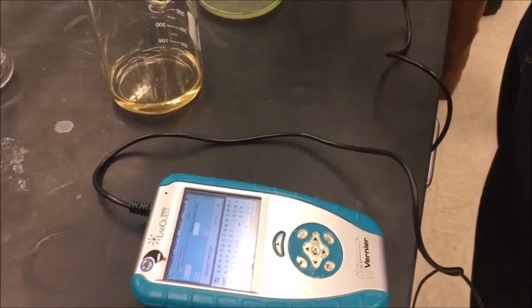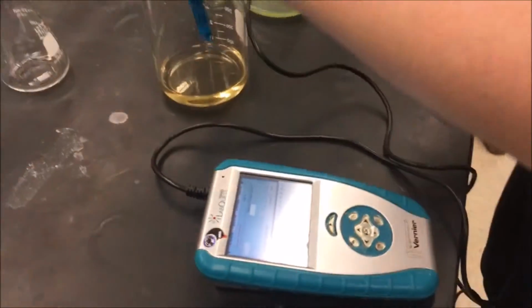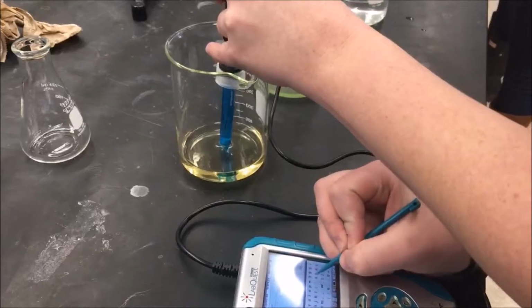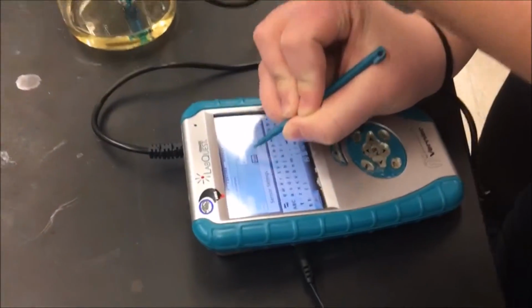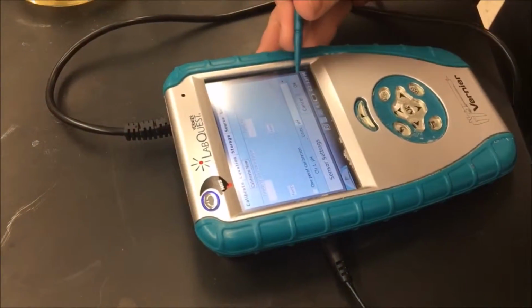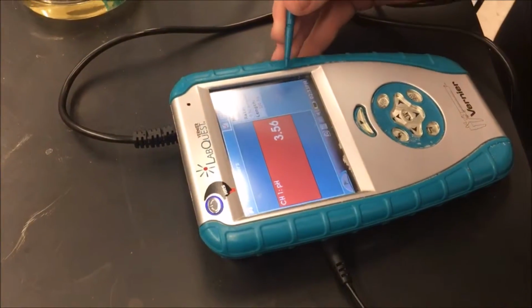When the probe is dry, place it in the beaker containing the pH 7 buffer. Once again, wait for the value on the pH meter to stabilize and then enter in the value 7. Press Keep, then press OK. Now the probe has been calibrated using the 2-point method.